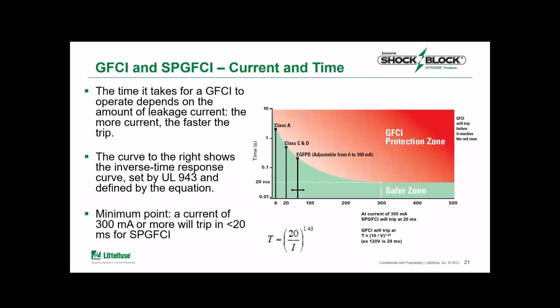Now, there is a minimum point shown on there with the dotted white lines at 300 milliamps for the special purpose GFCIs. And for any current that is above 300 milliamps, the device must trip within 20 milliseconds. The class A GFCI, in this case, would just be slightly slower, with a maximum trip time defined by that formula you see on the page, for those voltages where a class A GFCI applies.